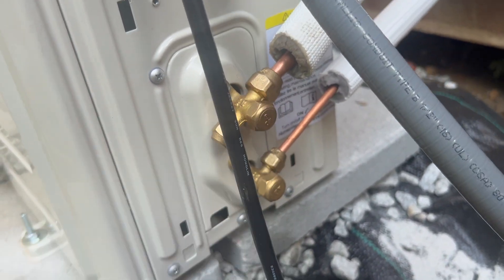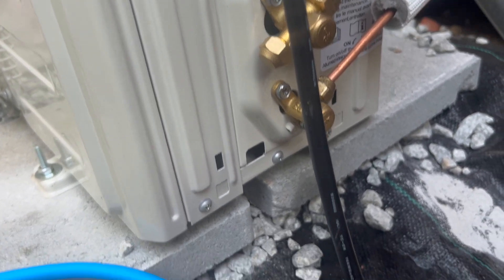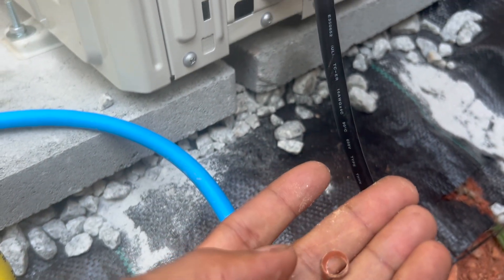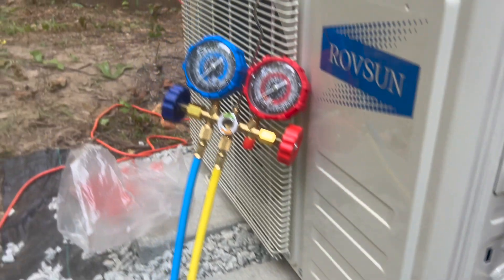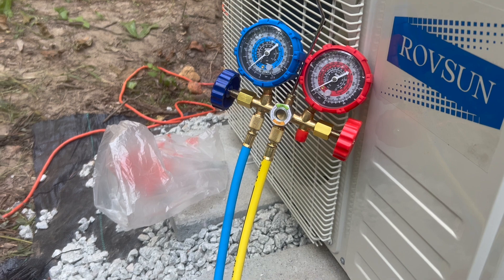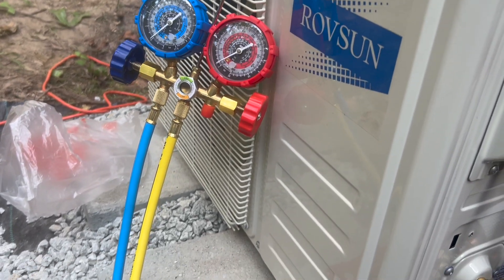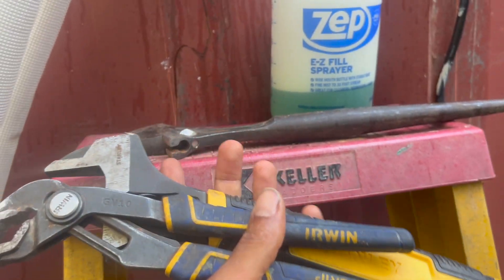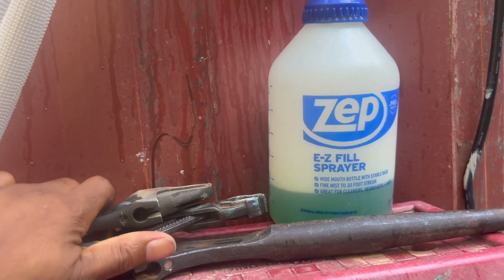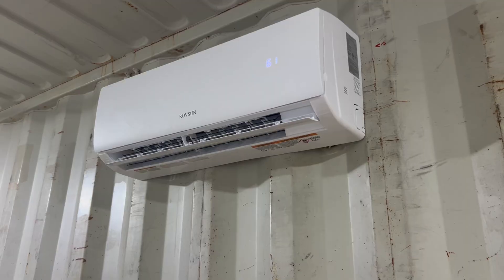That flare was leaking too, so I had to re-flare that. In a lot of videos, nobody ever has a leak except for me — I had two leaks. I'm just telling you: your leak is probably because you didn't torque the bolt down tight enough, or your flare isn't good. I recommend using a crescent wrench and a vise grip or channel lock because it gets it much tighter than two crescent wrenches.